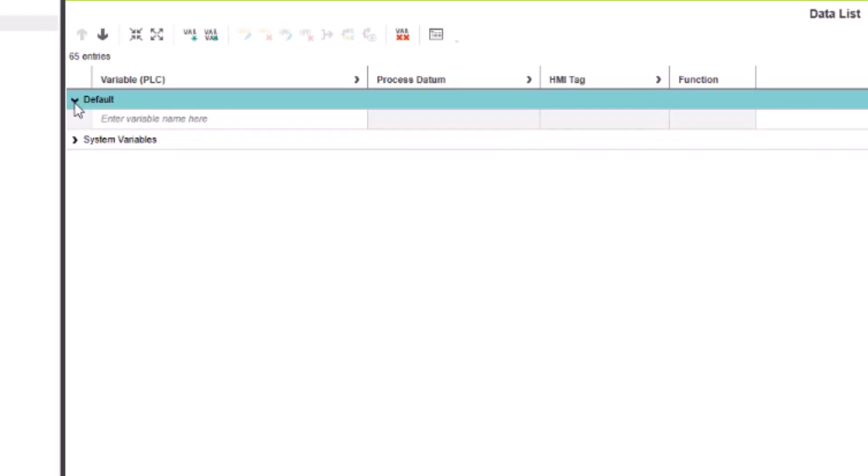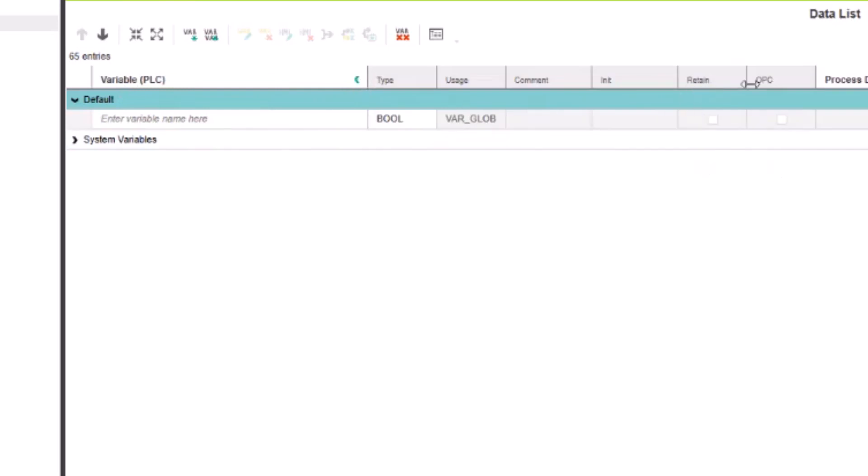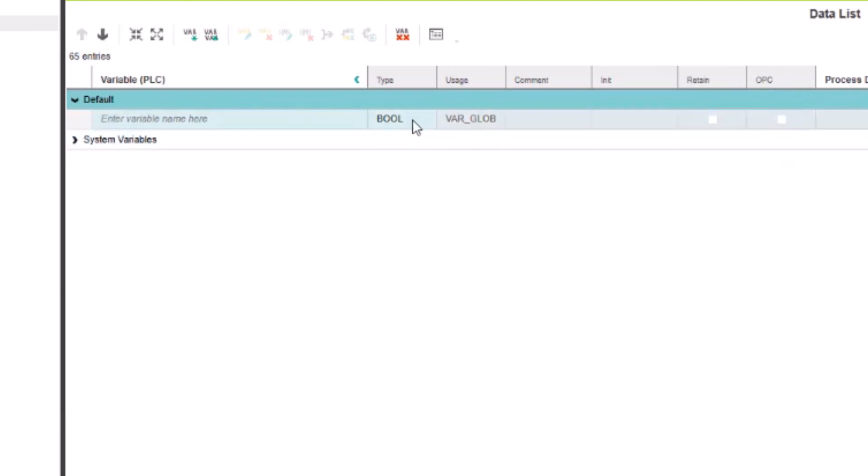So what I'm going to do is create two analog inputs, two analog outputs and maybe four digital inputs and four digital outputs so that we can use them with OPC UA. If you look here in the variable PLC, if you click on this little right arrow, it will open up and you can see right here is the OPC. Remember before I said if you don't have all clicked, you can individually select them and this is where once you've set up your variables, you could select them. Now just to clarify, analog inputs and outputs are word based and digital are booleans, bits. So I'm just going to go through and create these. As soon as I've got them all created, I will continue the video.